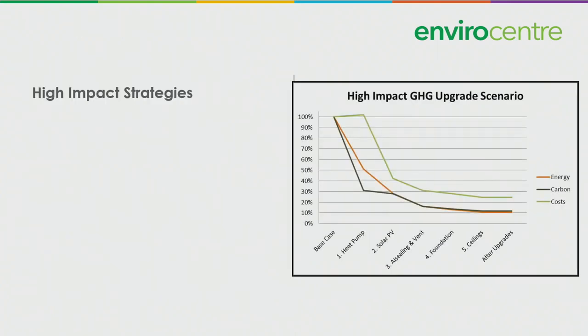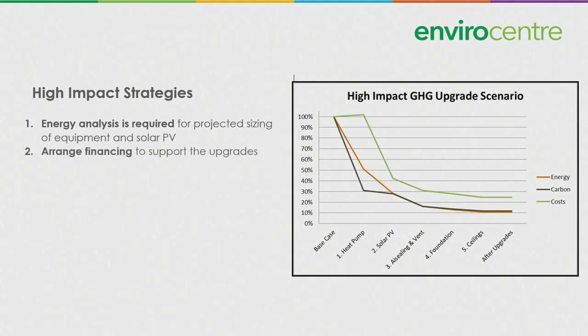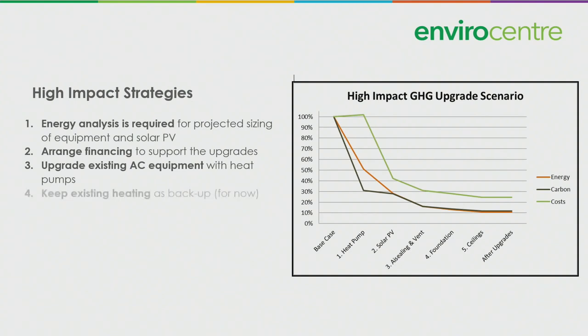So, high impact strategies. First of all, they require energy analysis. So you need to get an energy advisor in earlier to get the projected sizing of equipment and the solar photovoltaic cells. You have to arrange financing to support the upgrades because you're going to have more upfront costs. Upgrade the existing AC equipment with heat pumps. That's what I would recommend starting with. Keep the existing heating as backup for now. You don't need to replace your furnace or your boiler yet. Install your solar panels.